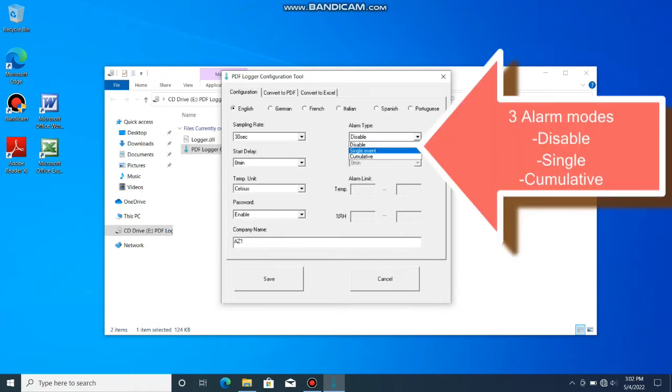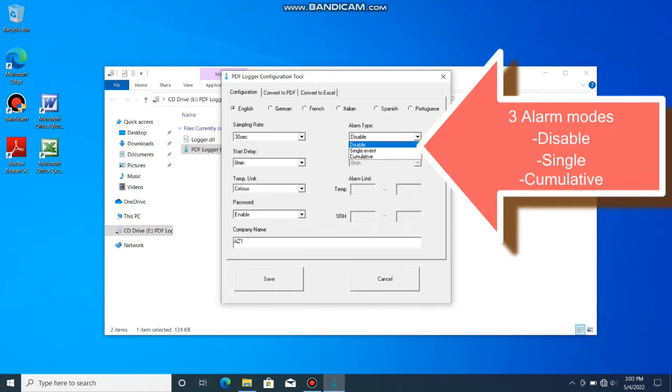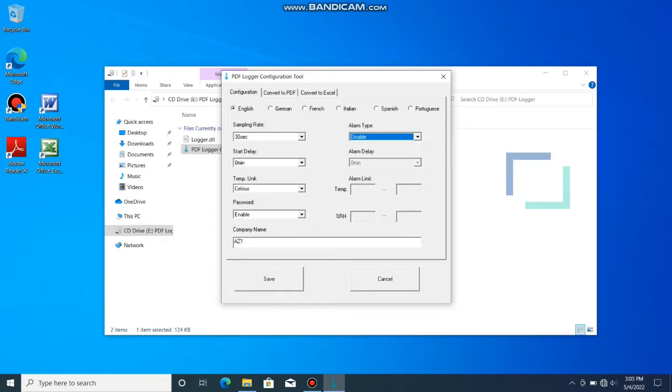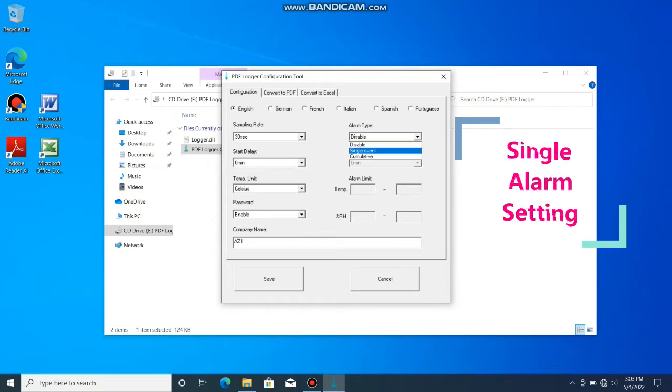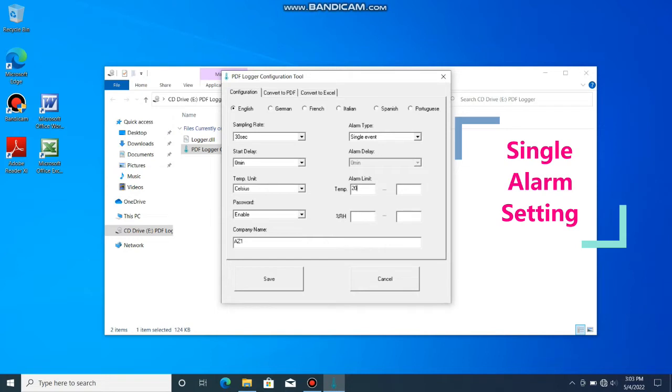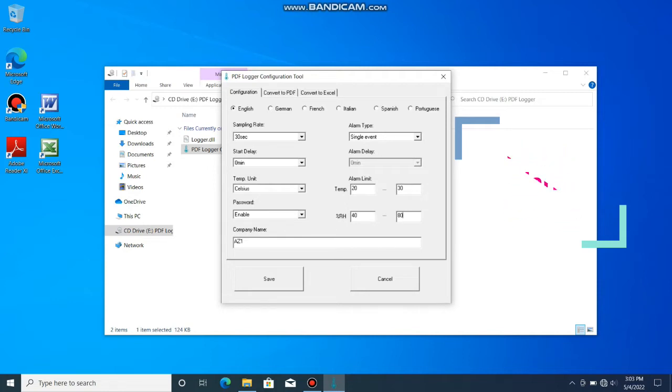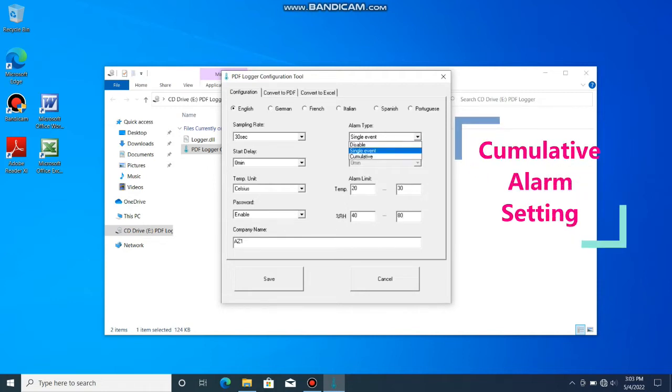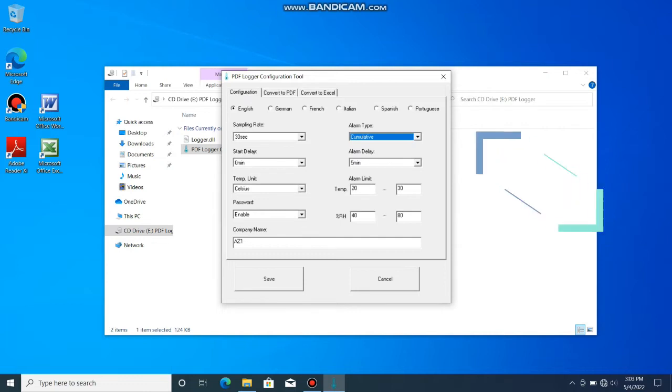Alarm: There are 3 alarm modes to select: disable, single event, and cumulative event. Single means one out of range event can trigger the alarm. Cumulative means the alarm will be triggered while the average value during alarm delay duration exceeds the alarm threshold.